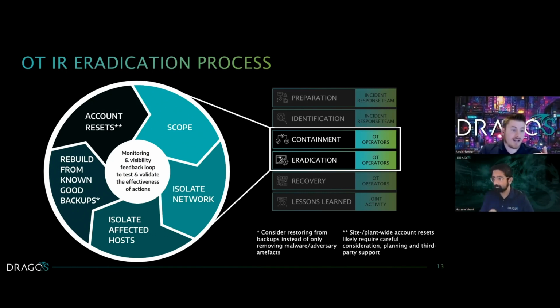Another thing is account resets. That's why we put 2 asterisks on this, because you have to be very careful when resetting account passwords in an OT environment, because there are many considerations such as shift change. Maybe the next shift can't do their job. That's probably a commonly used account across maybe 3 8-hour shifts. Maybe there are more rotations that you have to consider. And likely you're going to need to contact that vendor to reset all the accounts, especially the system accounts for that SCADA system.